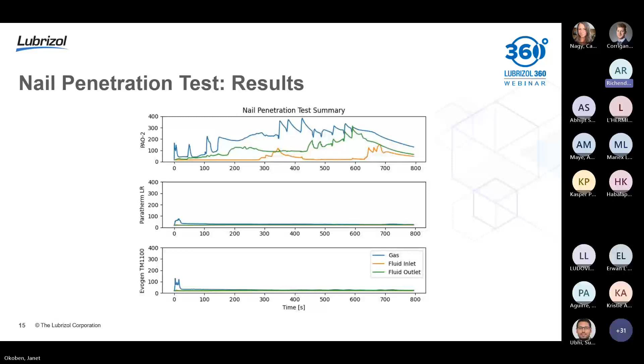Now if you look at the two Lubrizol fluids, both the Paratherm LR and the Evogen TM 1100, you can see you only have that initial spike. Only that first cell, the one penetrated by the nail, actually went into thermal runaway. After that there was no such event. So this is a good indication that these fluids, as well as the immersion cooling technology, were able to prevent the cascade of thermal runaway from one cell to the next.